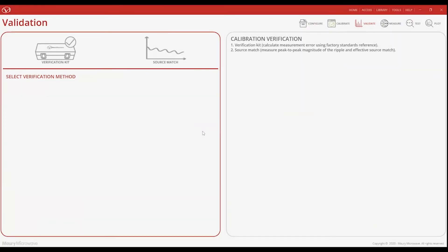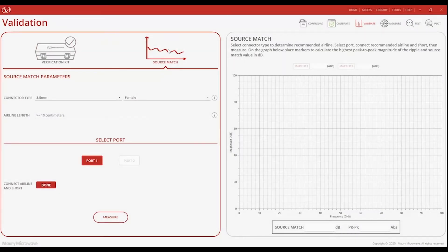In the validation menu, we can choose either the legacy source match technique using an airline and short, or the more definitive verification kit technique. Since it was the source match technique that likely led to ambiguity over whether the calibration was good or not, we will use the verification kit technique instead.